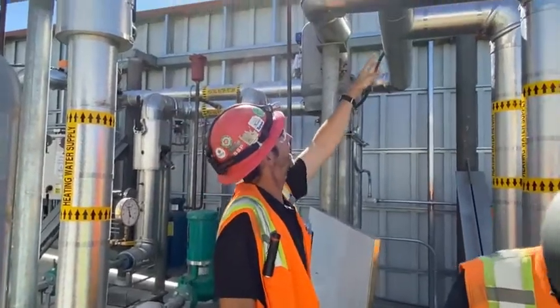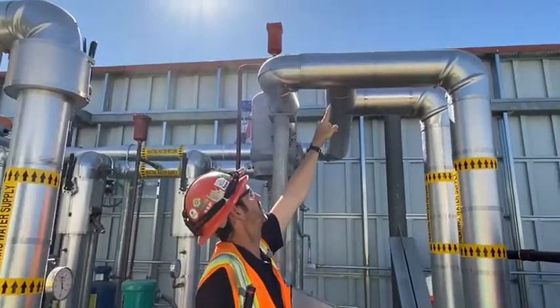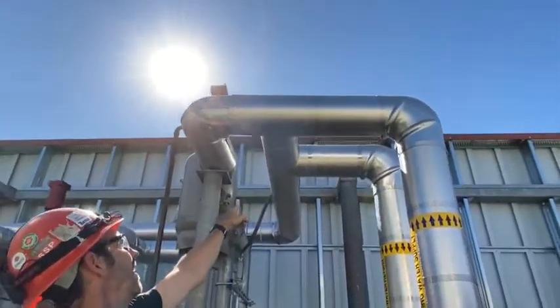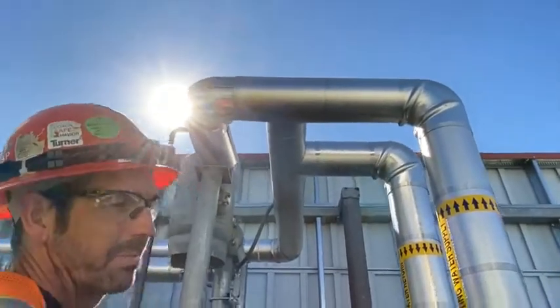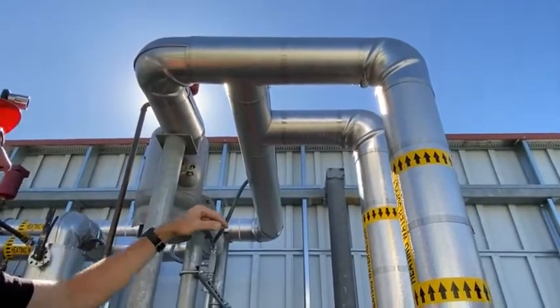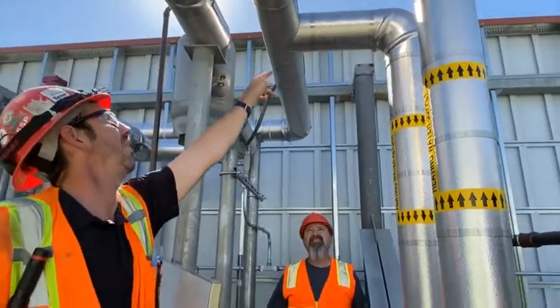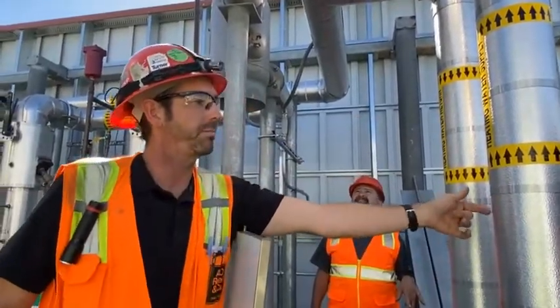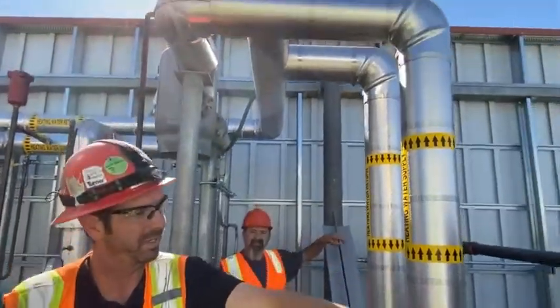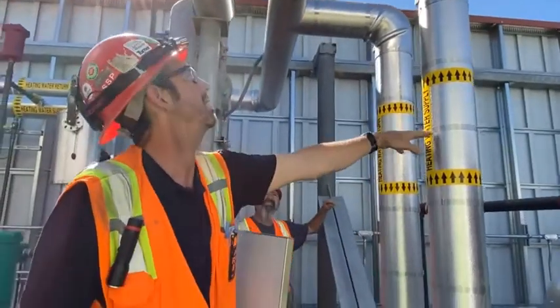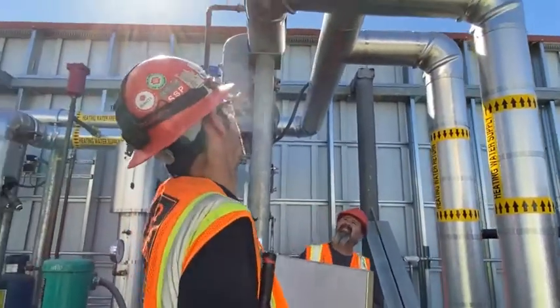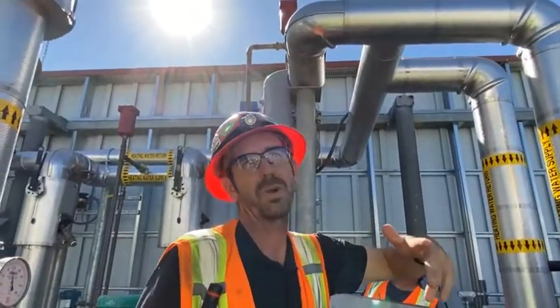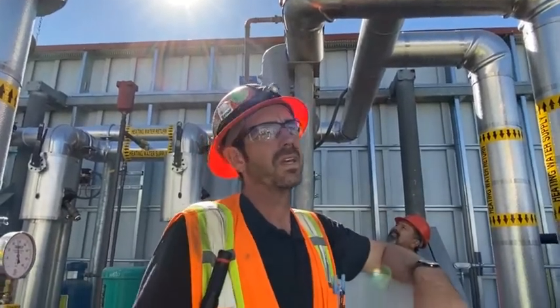We create a primary secondary here. This is a decoupler line in between the 2 pipes. So that allows the flow for the building pumps to pump water out to the building. But then it also allows water to get sucked out of that pipe, drawn through the boilers when a pump is running, and then it gets pushed back through this pipe and mixes in the water as it goes back into the main pumps. That's your primary, secondary, okay?